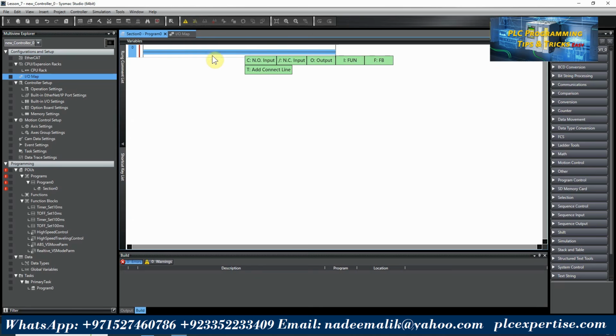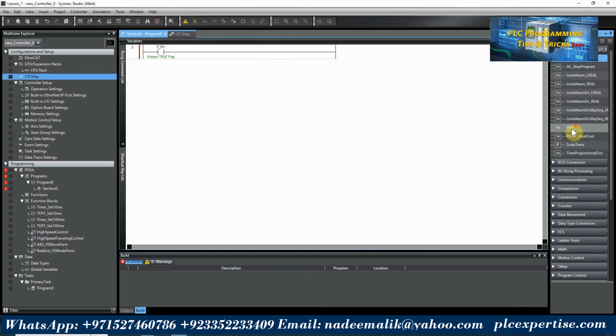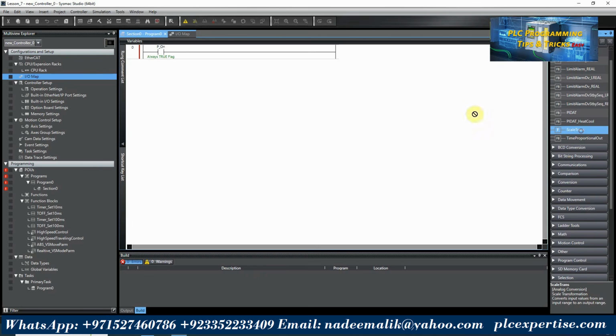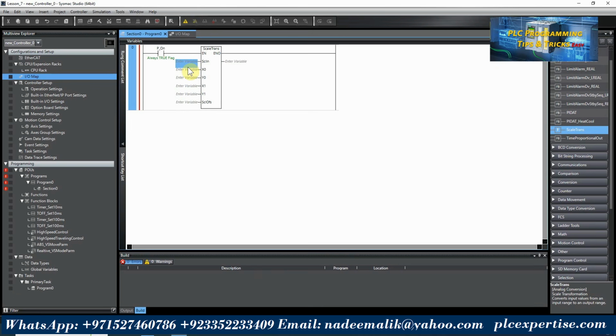First of all, we will insert here a contact and name it as P on flag, which is always on flag. Next, we will go to the analog conversion and here we will select and drag and drop this scale trans block. Next, scale in is a speed reference signal and we can write here VFD signal reference. Enter, and here we will generate another variable and this data type will be real.